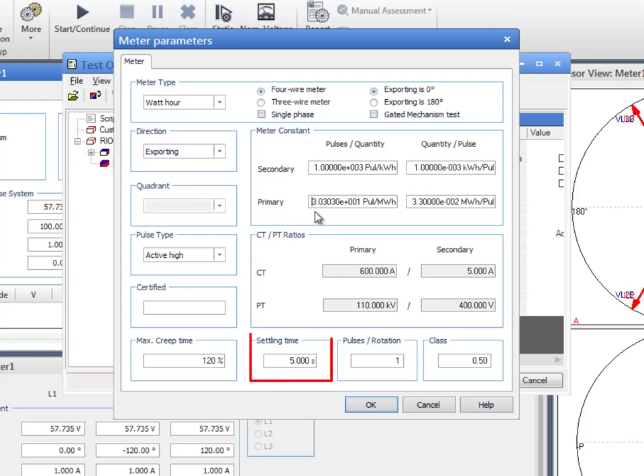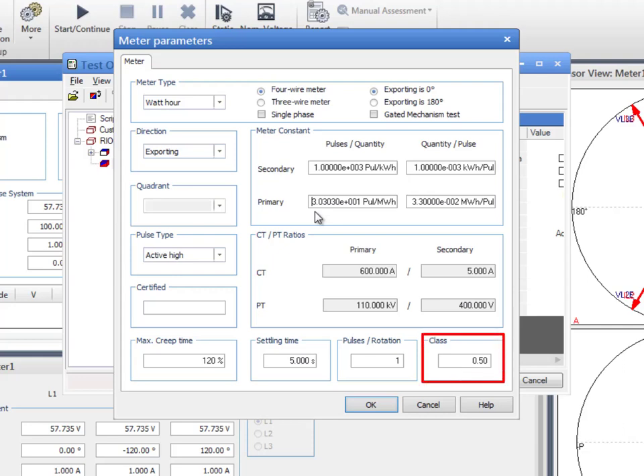The settling time allows the meter to establish a stable operating state, so that the meter is able to perform a reliable and stable measurement. Search for this setting on the respective datasheet. For this test, we will keep the default value of 5 seconds. For the evaluation of the test results, the value for the tolerance has to be specified in the class field. In our example, the value will be set to 0.5.